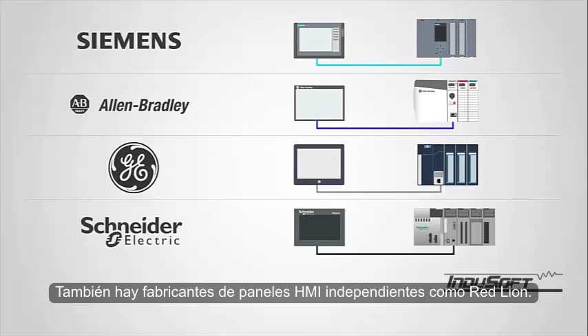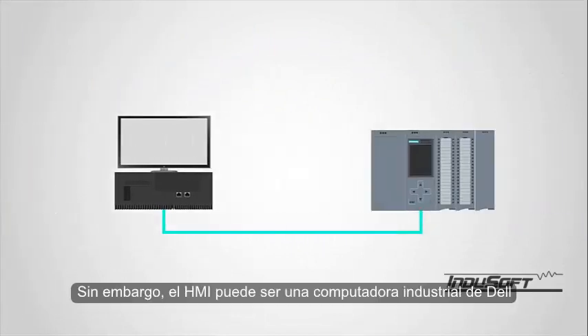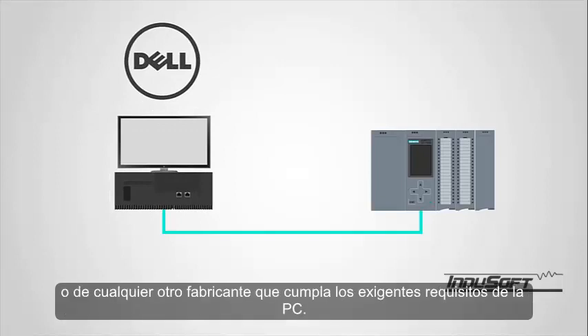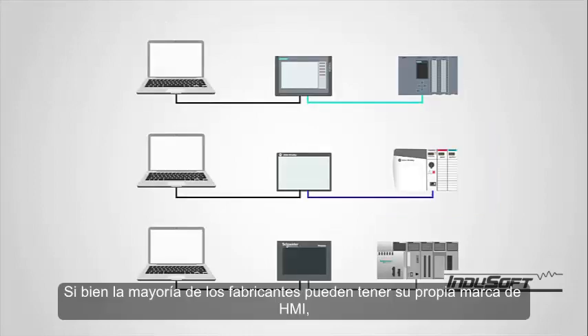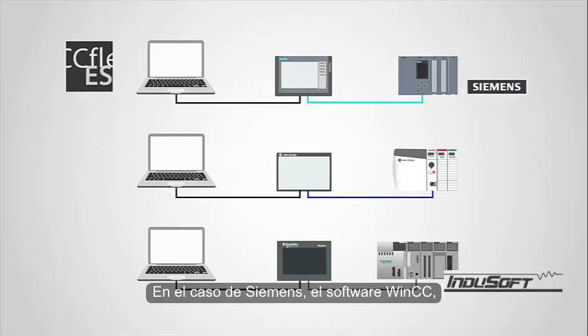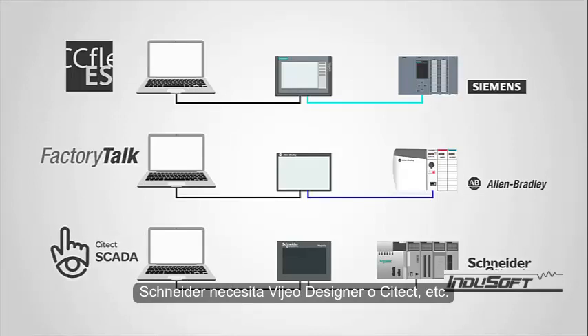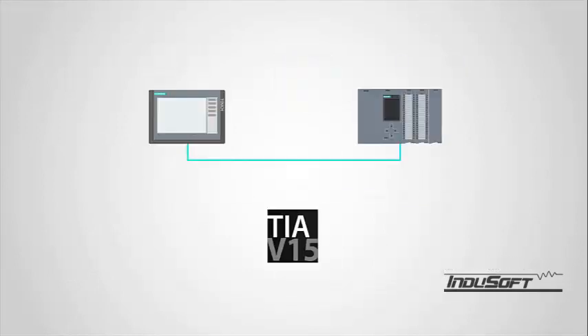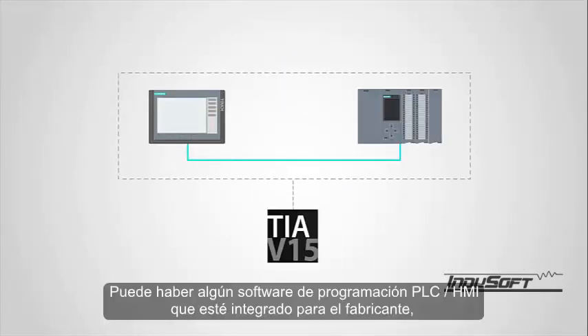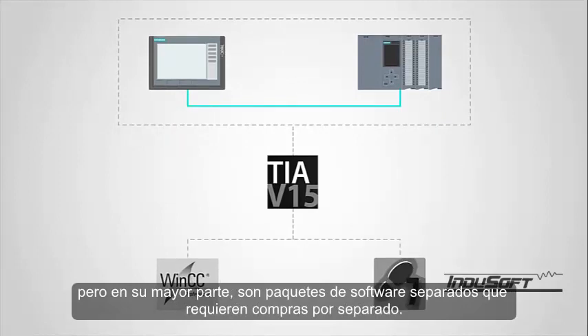There are also independent HMI panel manufacturers, such as Red Lion. The HMI can also be an industrial computer from Dell or any other manufacturer that meets the rugged requirements for the PC. While most manufacturers may have their own brand of HMI, typically additional software is needed to program the HMI. In the case of Siemens, WinCC software; Allen-Bradley requires Factory Talk View; Schneider needs Vijeo Designer or Citect, and so on.